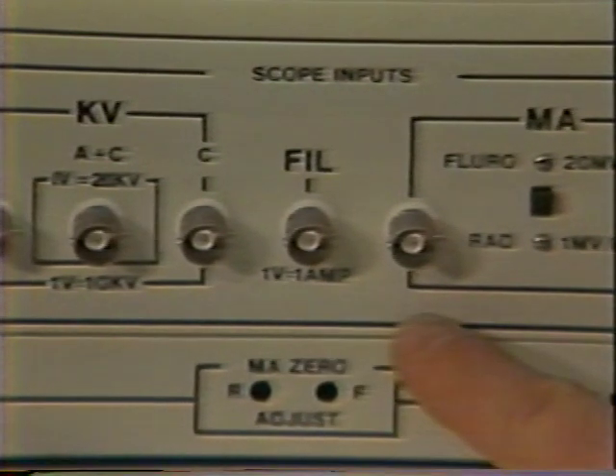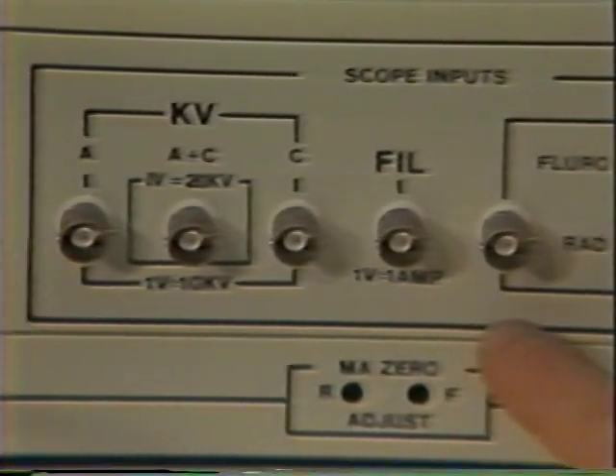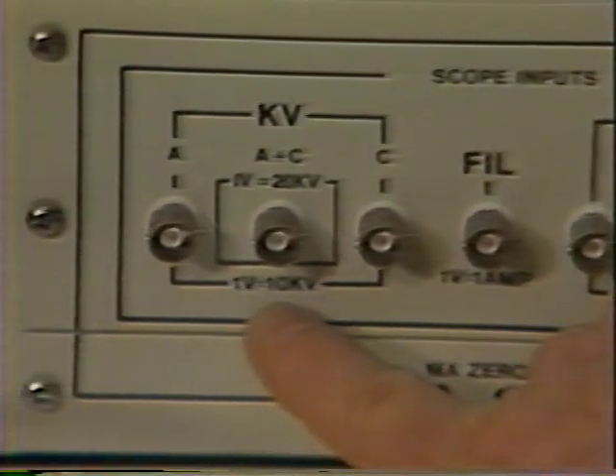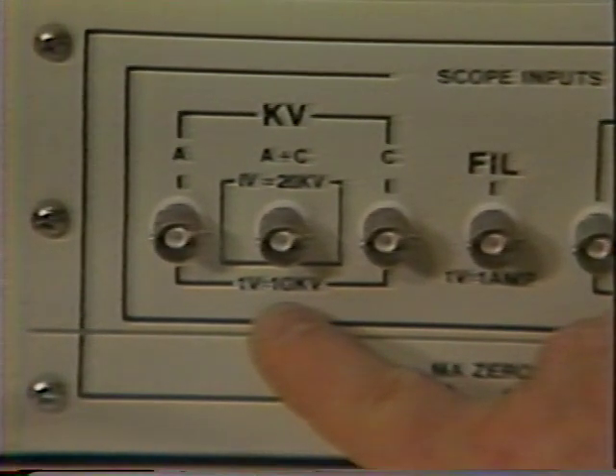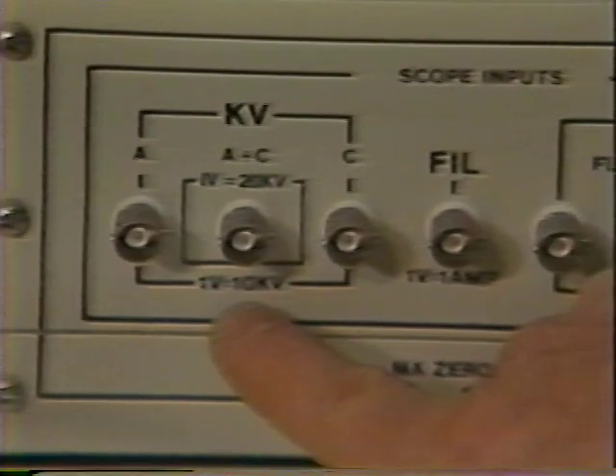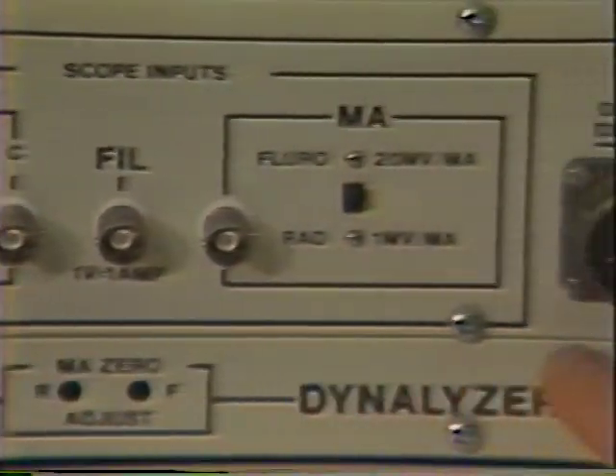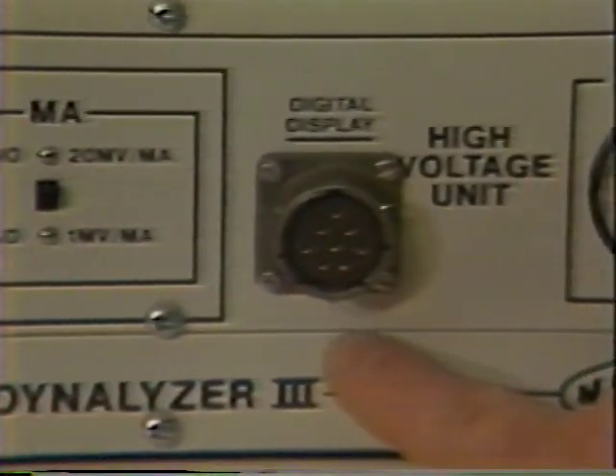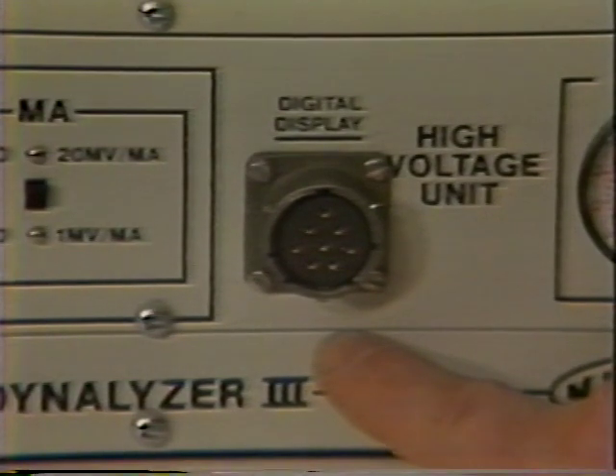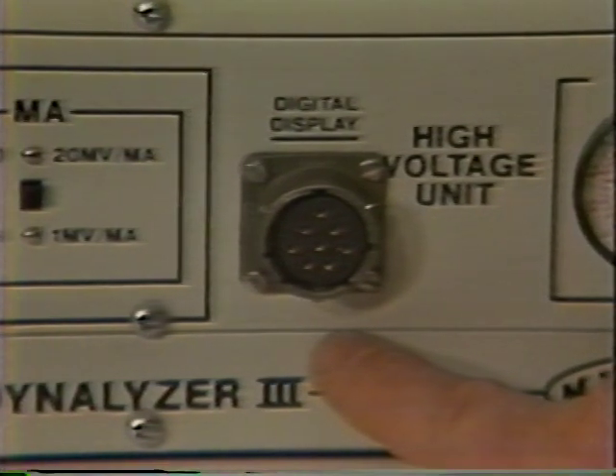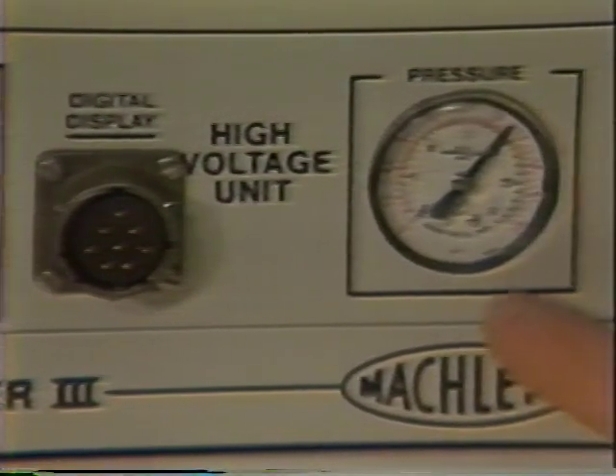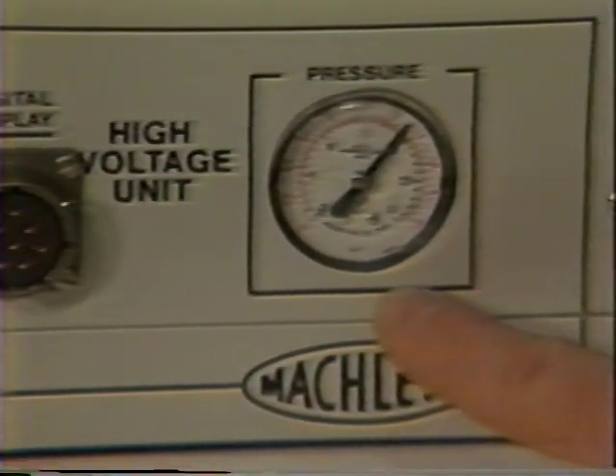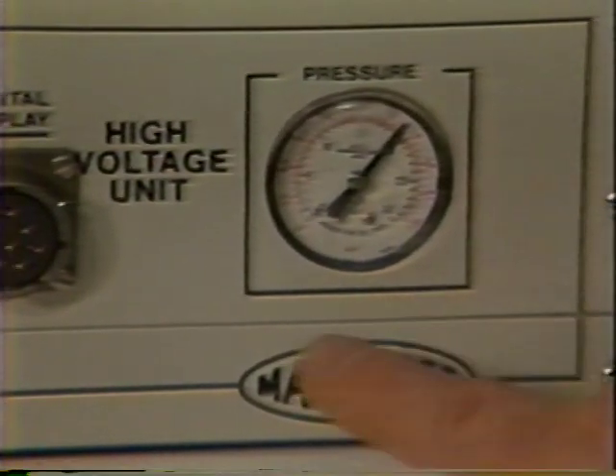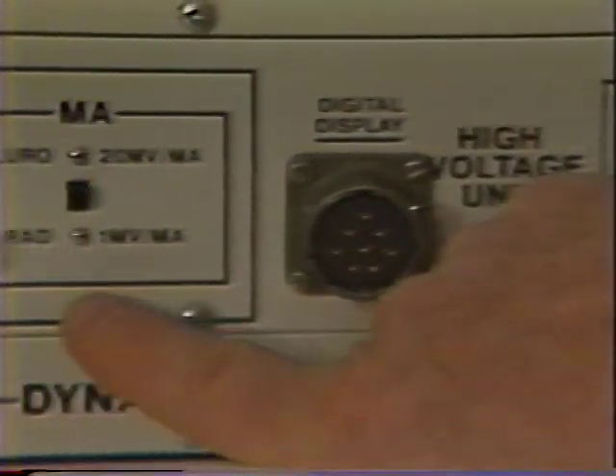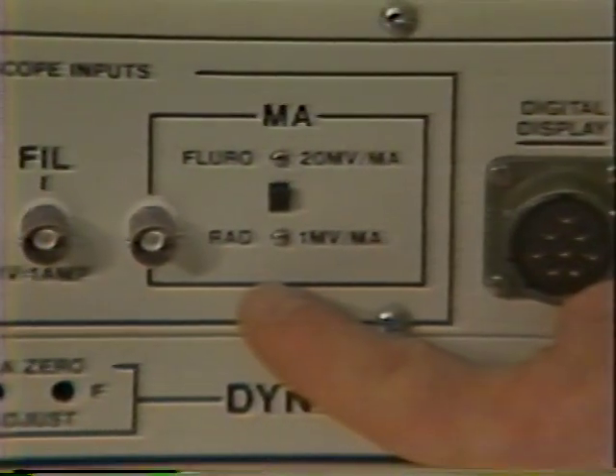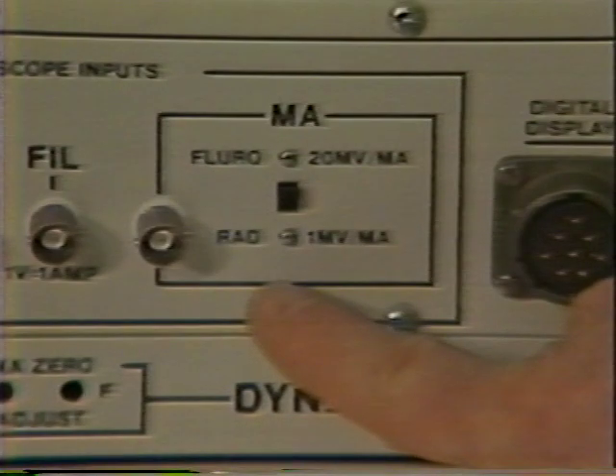An addition that we've made on Dynalyzer 3 over the Dynalyzer 2 unit is a coaxial connector to look at the summed KV. We also have a connector here where we take a 20-foot jumper cable from this unit to the back of the digital display and take that in the booth with us. We have a pressure gauge which indicates the pressure of SF6 gas which we have inside the unit. The other addition that we've added to Dynalyzer 3 over Dynalyzer 2 was the capability of changing the sensitivity of reading MA.